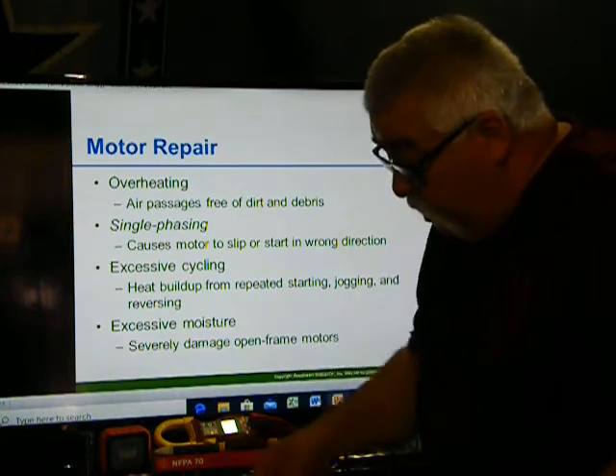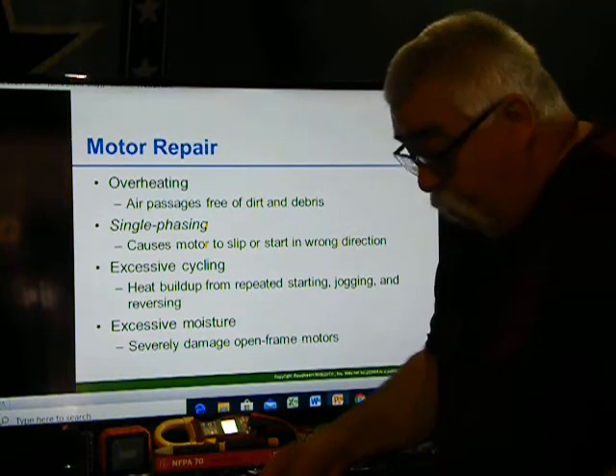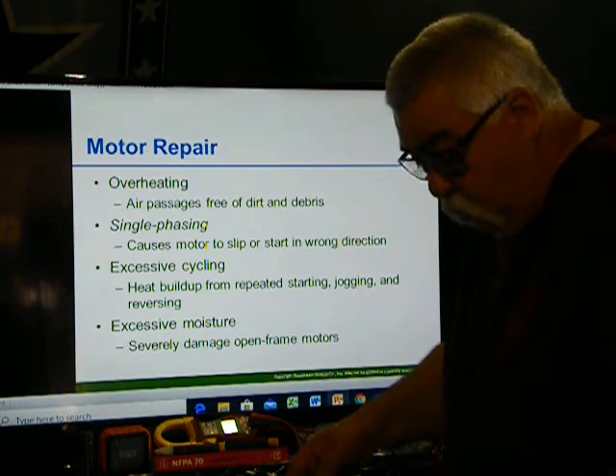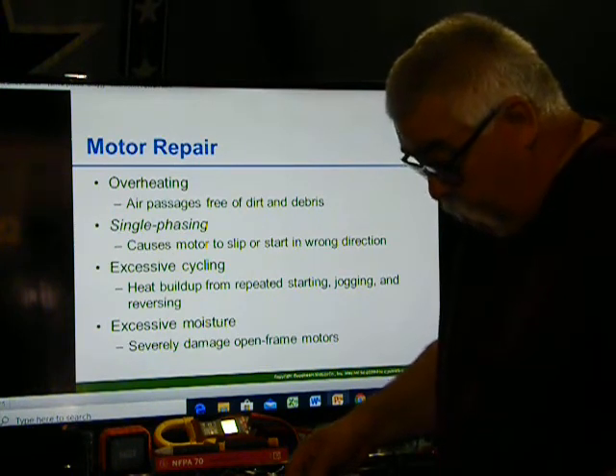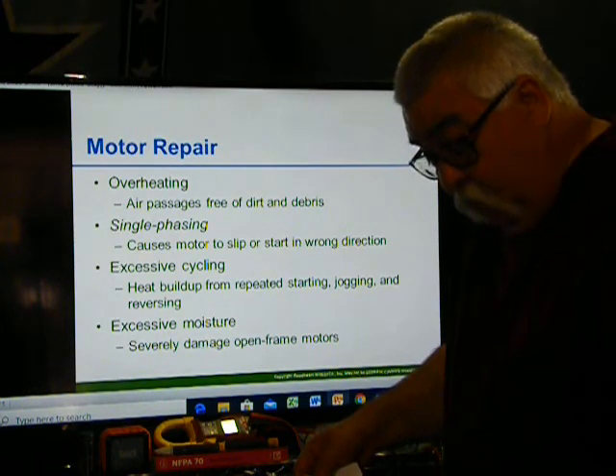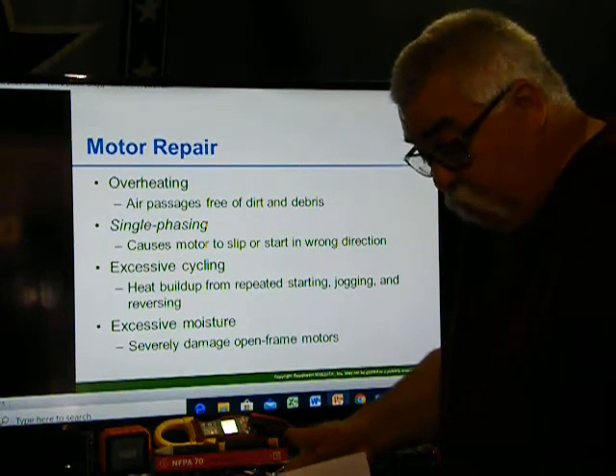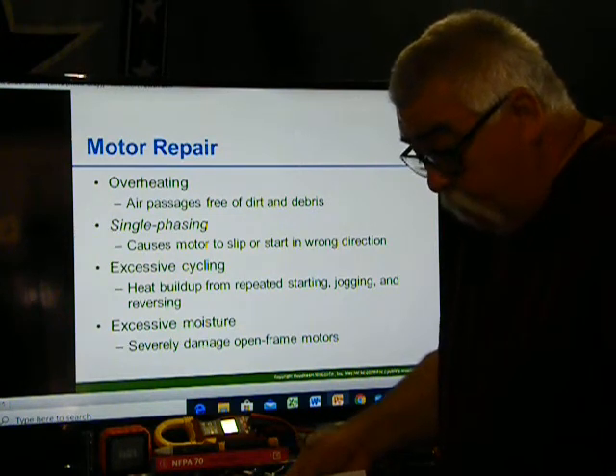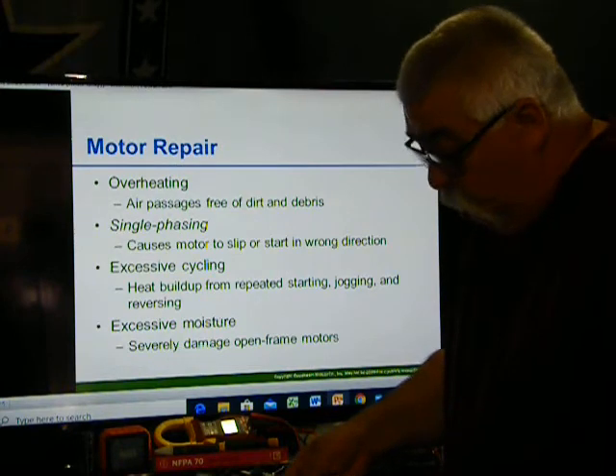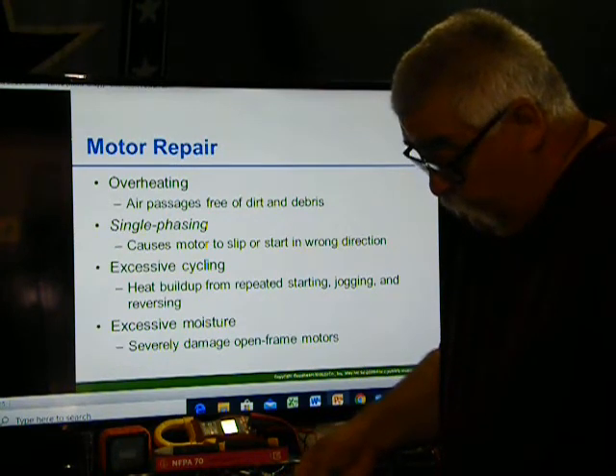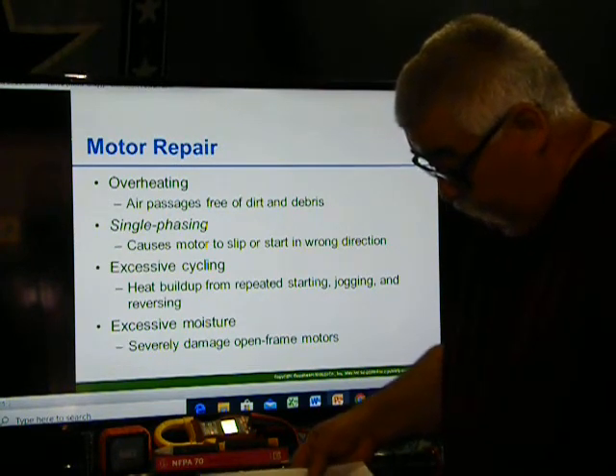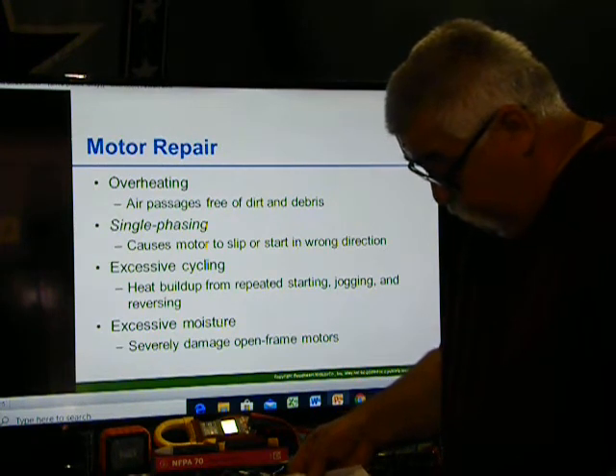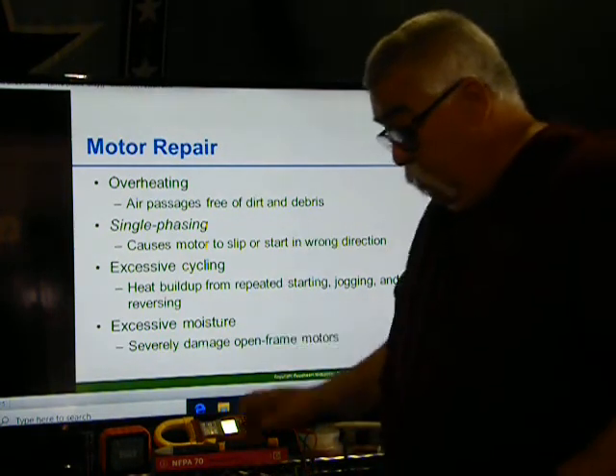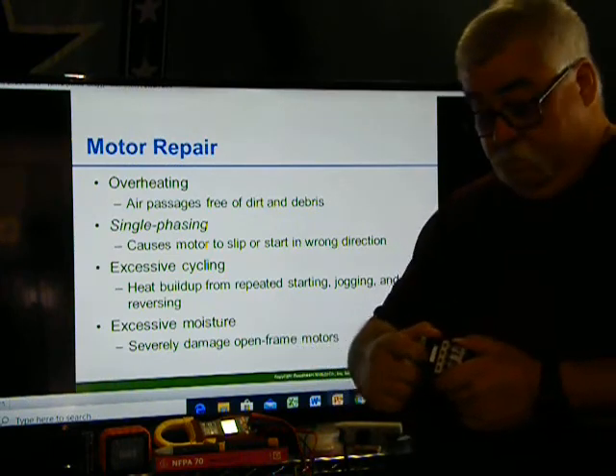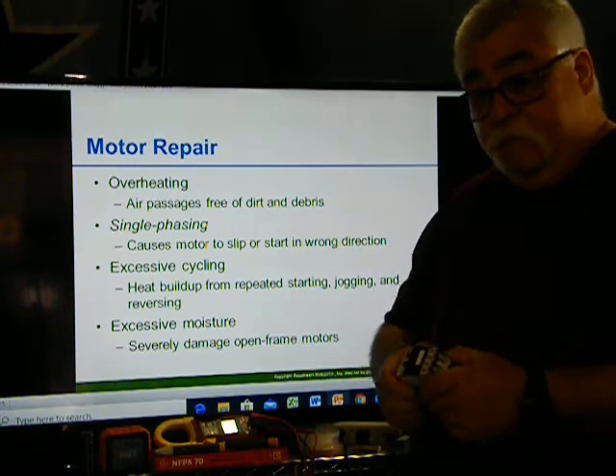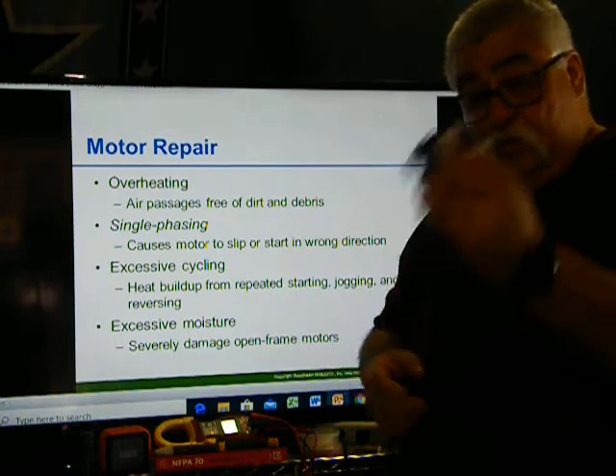On page 250 and 251, it says motor control troubleshooting chart. So take a look and go through it. I'm not going to cover it. You can read some of the conditions for the contacts, the coils, overload relays, magnetic and mechanical parts, pneumatic timers, limit switches, manual starters when you turn them on manually. These coils can go bad. This one you can't replace, so you have to change out the whole thing.